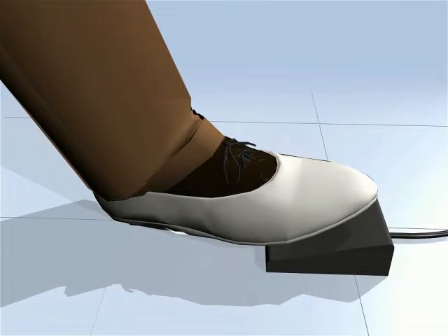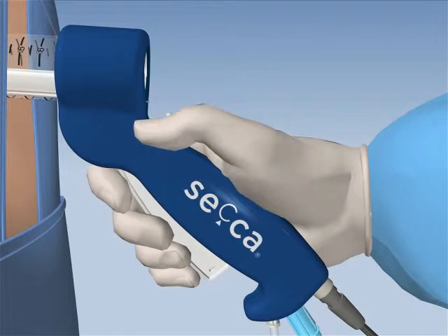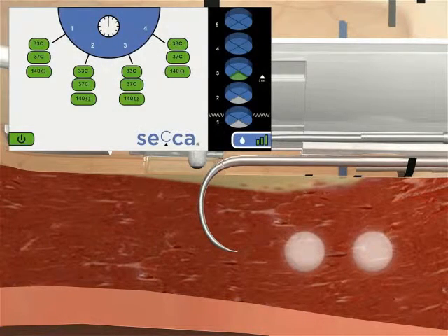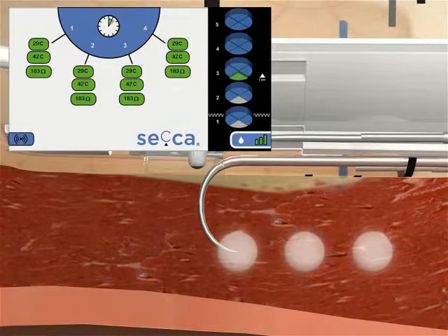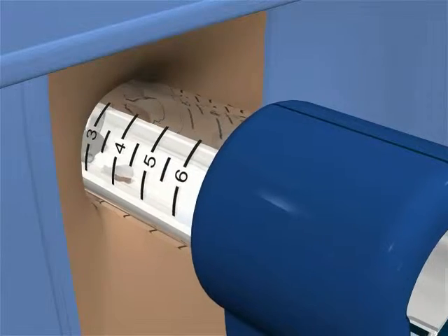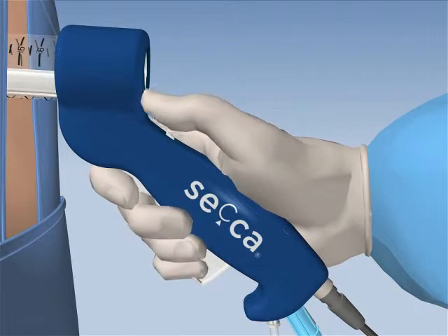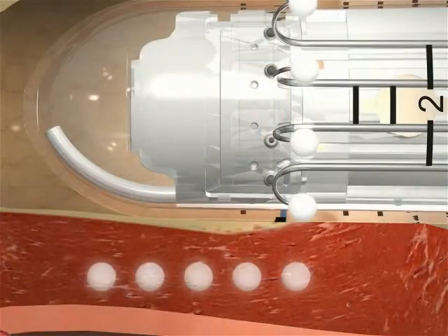Press the foot pedal to deliver RF energy. Monitor temperatures and impedance and adjust if necessary. Retract the needles after the treatment is complete. Advance the Secca handpiece 5 millimeters to Level 3, then extend the needles, observe temperatures and impedance, press the foot pedal to deliver RF energy, monitor, and retract the needles after treatment is complete. Advance 5 millimeters to Level 4, extend the needles, treat the tissue, and retract the needles until all 5 levels are complete. Quadrant 1 is complete. Be sure to retract needles before moving to the next quadrant. Rotate the Secca handpiece 90 degrees clockwise to the second quadrant and line up the solid black line with the dentate.